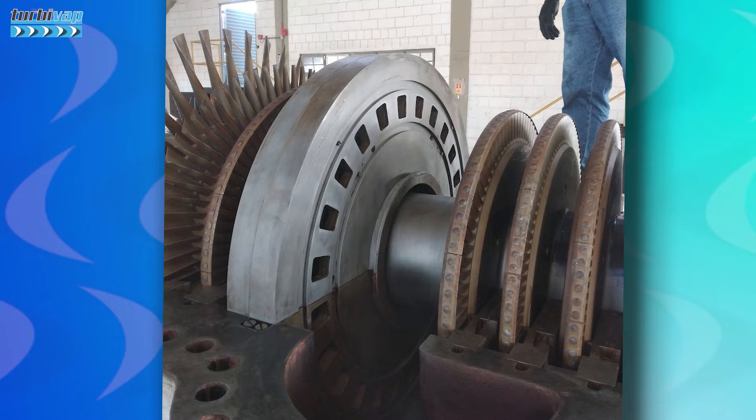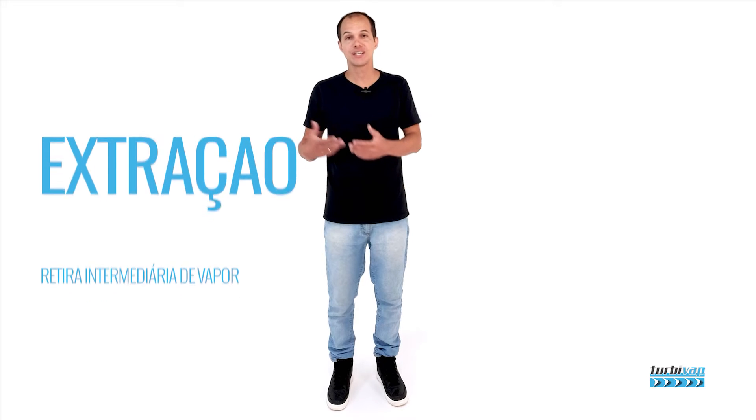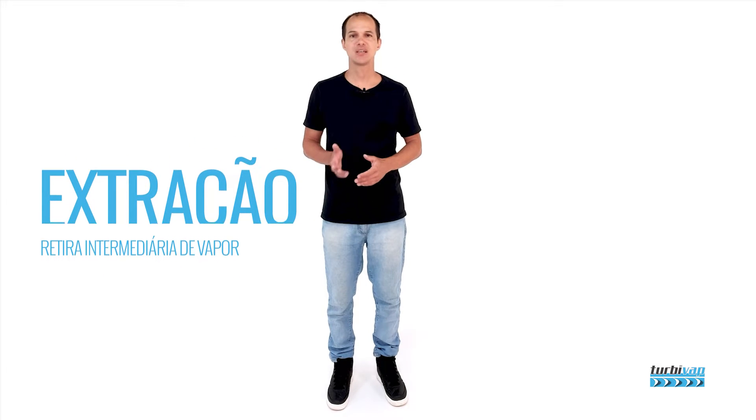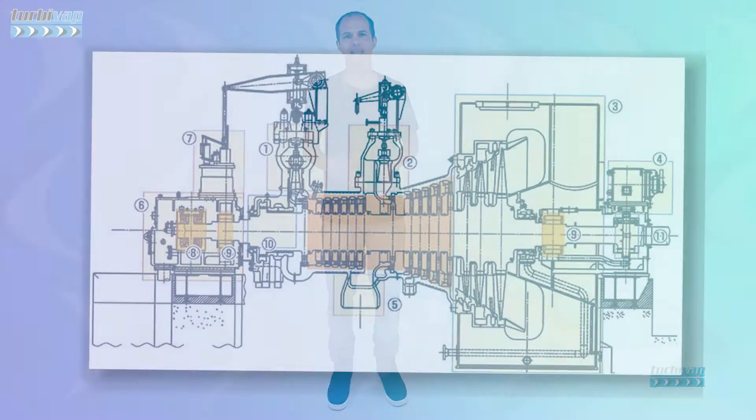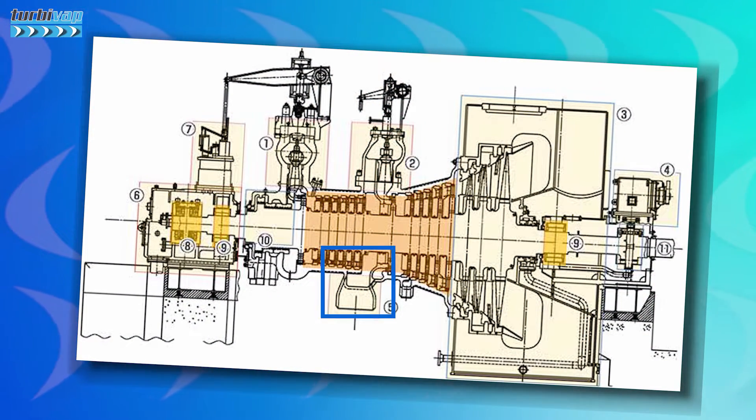Turbines can also be classified as with or without steam extraction. Extraction is nothing more than removing steam from within the turbine after passing through some stages. The steam enters the turbine with high potential energy, and after passing through some stages, part of this vapor leaves through extraction and goes to the process. The part that remains in the turbine expands until it exits through the turbine exhaust.